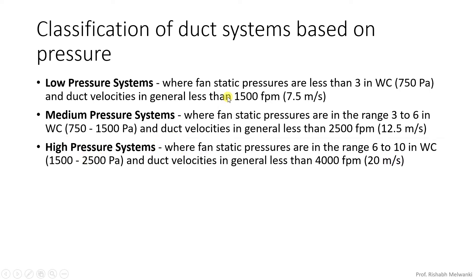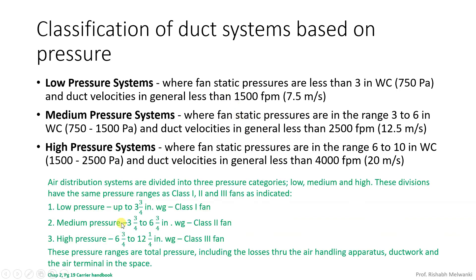Now we have talked about static pressure. What about total pressure? Based on total pressure this classification is found in the carrier handbook chapter 2 page 19. There you will find a low pressure system where total pressure is 3 and three quarters of an inch of water column in gauge — this is called a class 1 fan. Then medium pressure: 3 and three quarters to 6 and three quarters of an inch of water column in gauge — this is called a class 2 fan. When you consider high pressure it is 6 and three quarters to 12 and a quarter inch of water column — that is a class 3 fan.